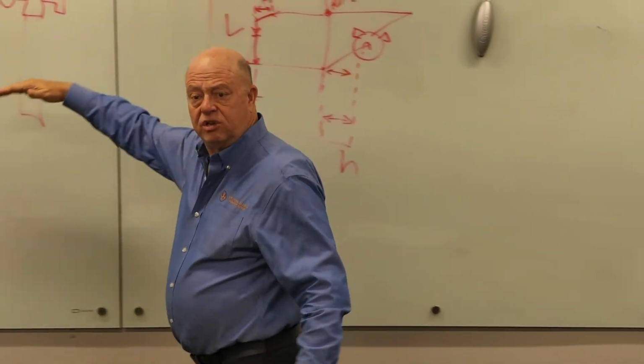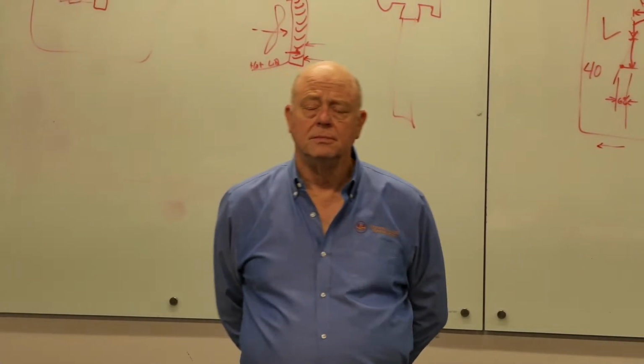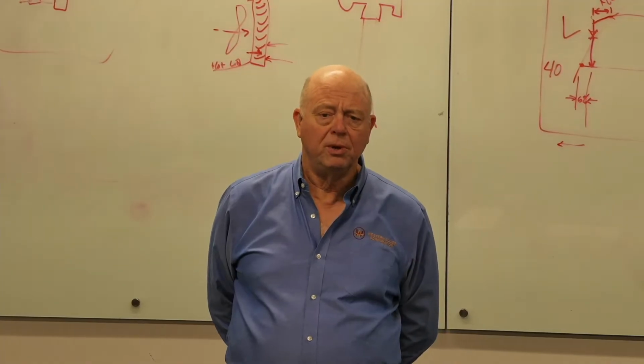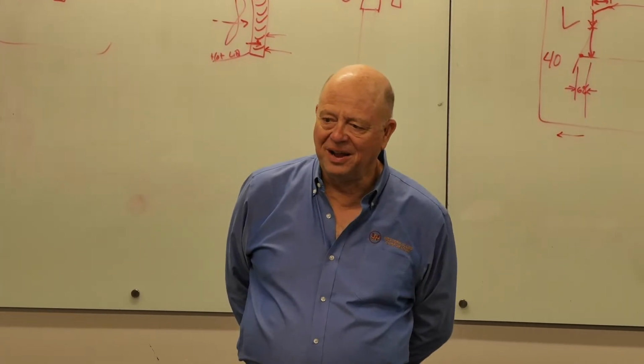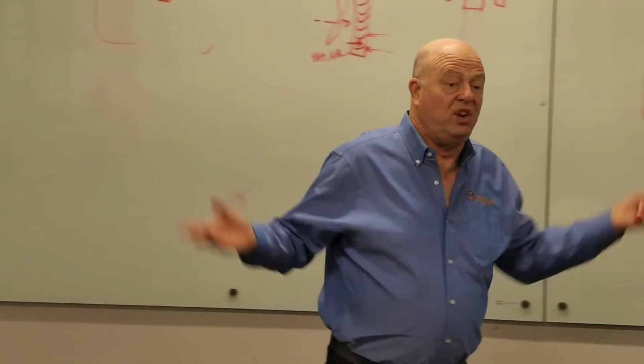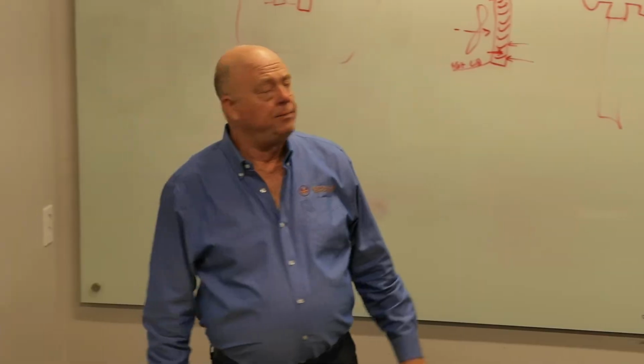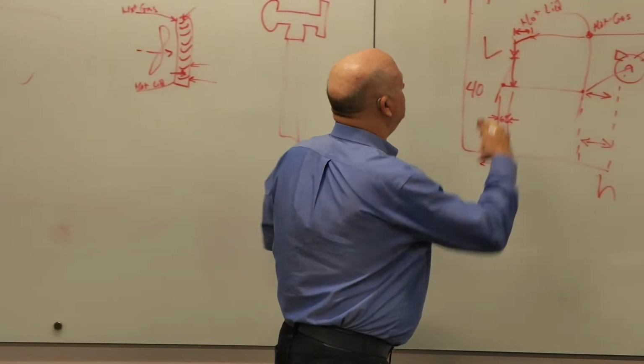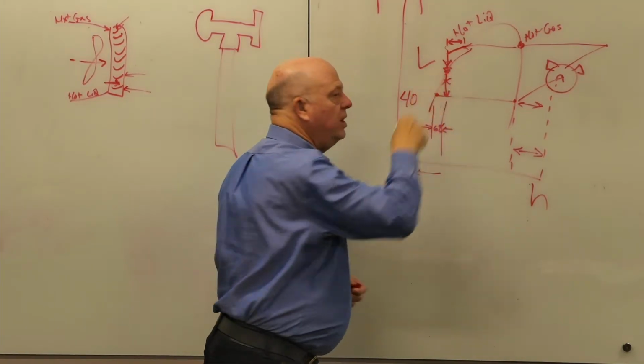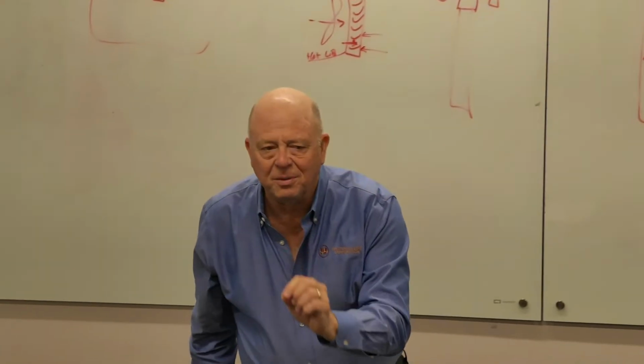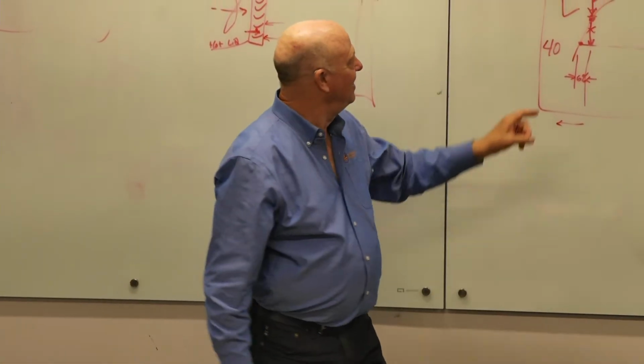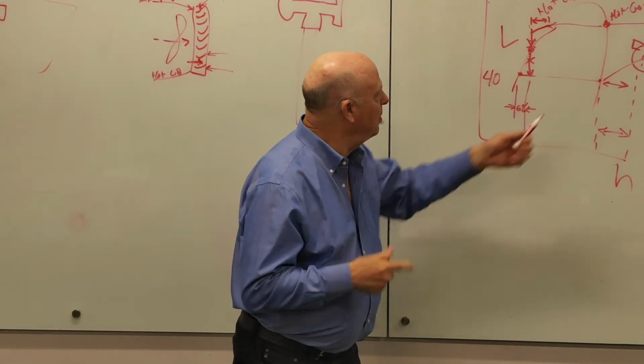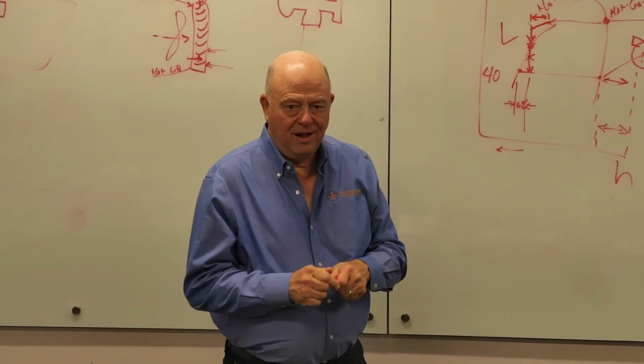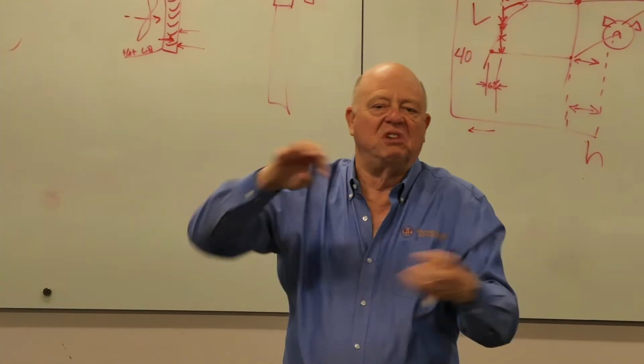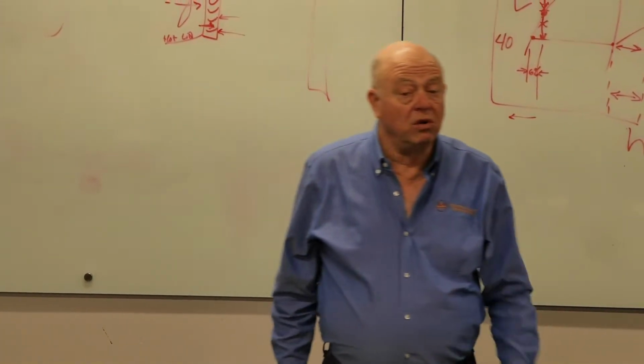What about, we talked about the gas line and the condensation. What happens in the liquid line? Do we get a lot of subcooling? Because it gets so cold. Because it's just sitting there, and it's going to end up eventually the temperature of the ground, whatever it is, right? And so if the ground's 58 degrees, that's going to be the temperature of the liquid. And if the liquid gets too cold, the expansion valve doesn't completely work right. And if the expansion valve doesn't completely work right, we end up not being able to achieve superheat. So there's a bunch of kind of related reasons.